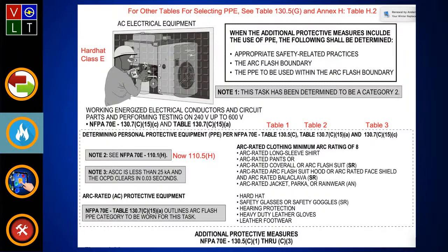And so the heavy duty gloves, as we said, 130.7C10, those heavy duty gloves go up to about 10 cal, real easy, and really up to about 12 for some of them, and you'll find that in that section. Then your leather footwear - if you exceed 4 cals per centimeter squared, you need to wear leather footwear or something equivalent, in accordance with the informational note listed there. Basically those are the methods you could use with the tables.